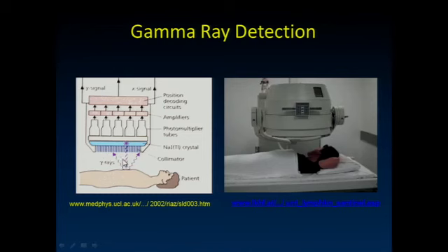Beneath that is our sodium iodide crystal. When one of these gamma rays interacts in the crystal, we get the production of lower energy visible light, which is readily detected by our photomultiplier tubes. Unlike our X-ray imaging, we're going to have really tiny detector elements because we need really high resolution imaging. In X-ray imaging I flood the patient with X-rays in a very short period of time. Here I'm going to image a longer period of time, and these events are going to occur far enough in space and time relative to each other that I can detect each one individually.